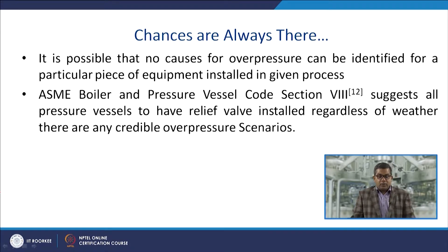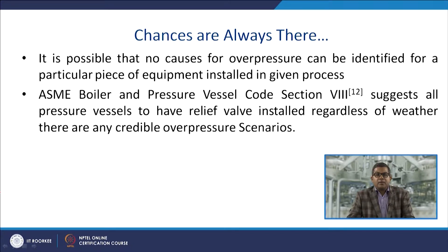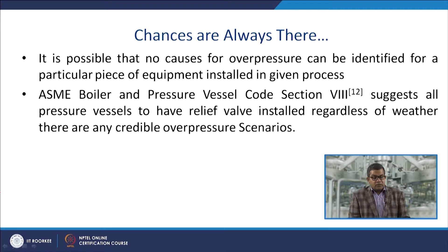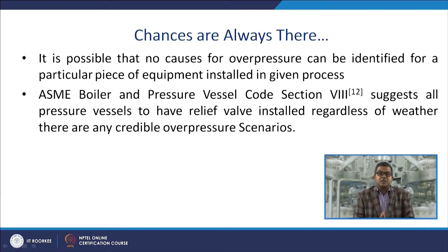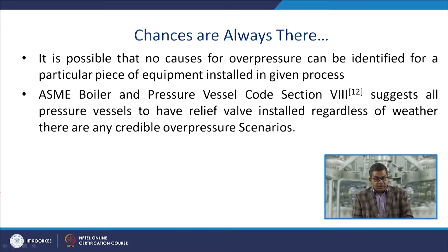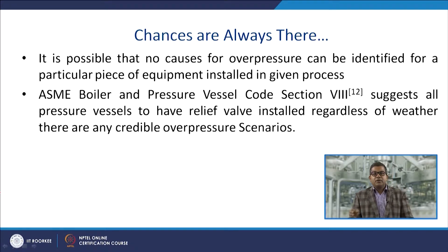It is possible that no cause for overpressure can be identified for a particular piece of equipment. However, ASME Boiler and Pressure Vessel Code Section 8 requires that all pressure vessels have relief valves installed regardless of whether there are any credible overpressure scenarios. This is mandatory, and in the Indian context there is a separate boiler certification code.